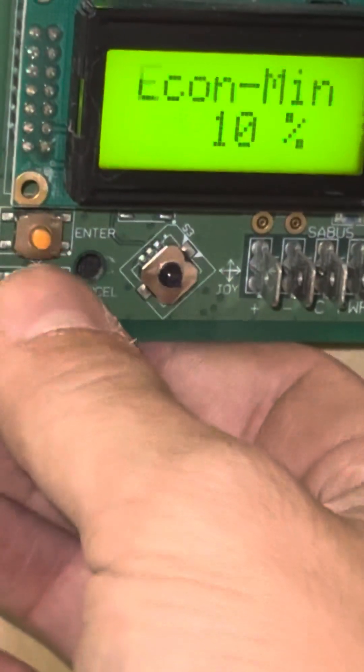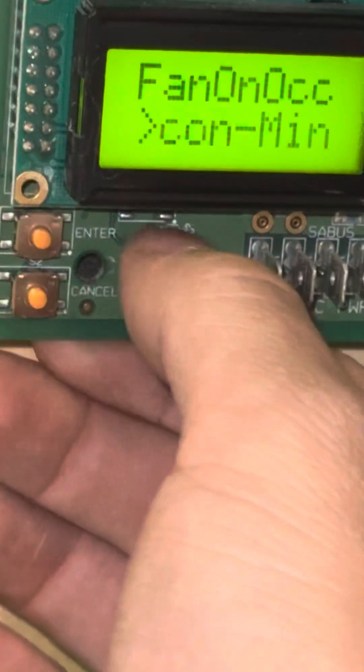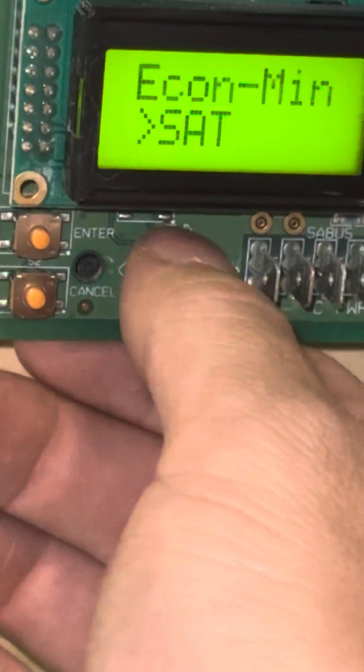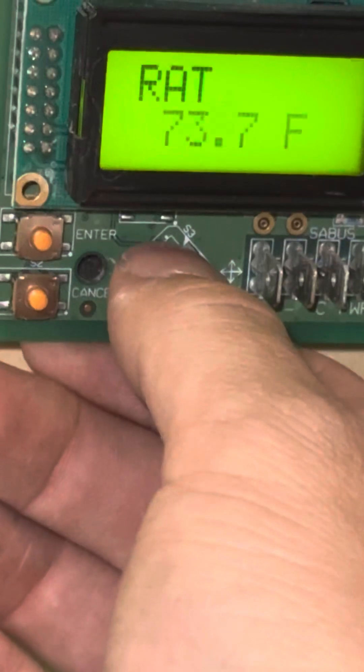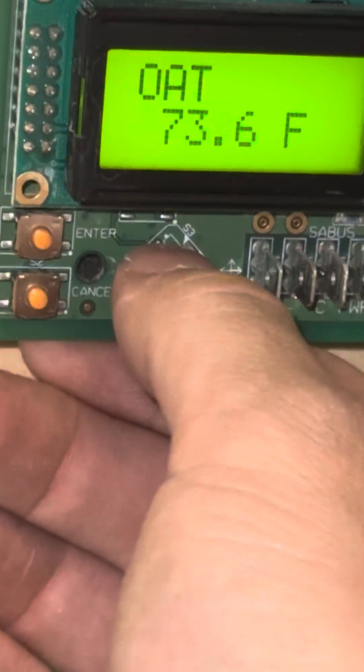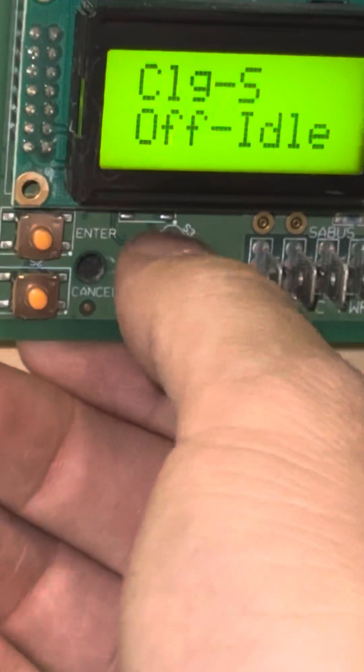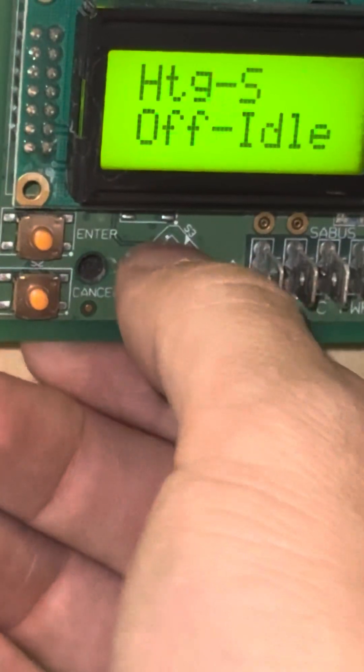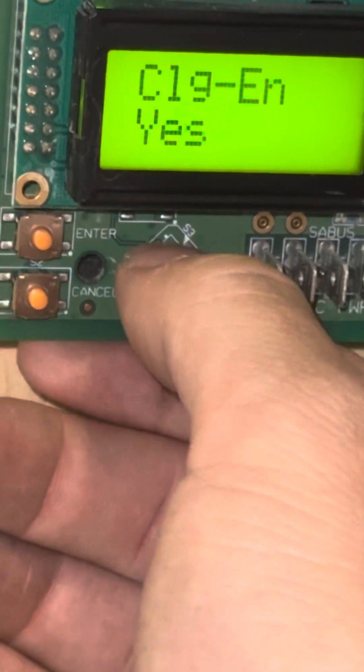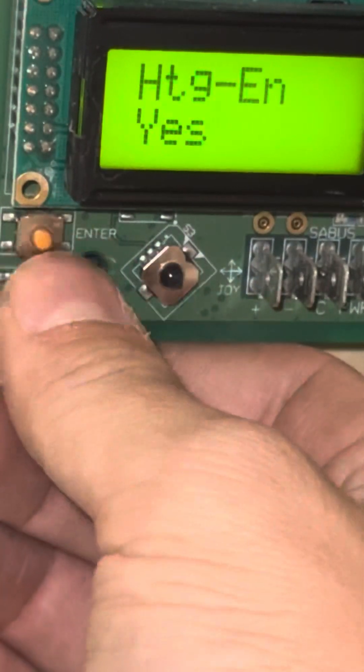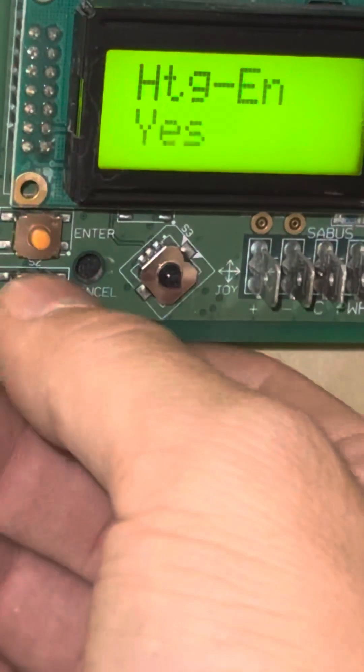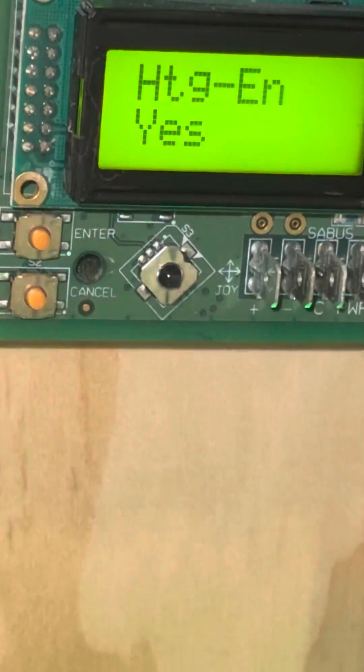I can see my SAT, I can see my return air temp RAT, OAT, my cooling status, my heating status. Is my cooling enabled? I can change it from here. I can change my heating enabled as well by pressing enter and switching it to no. If I have a defective gas valve or something and I just want to make sure to take the extra step and keep the heating disabled.